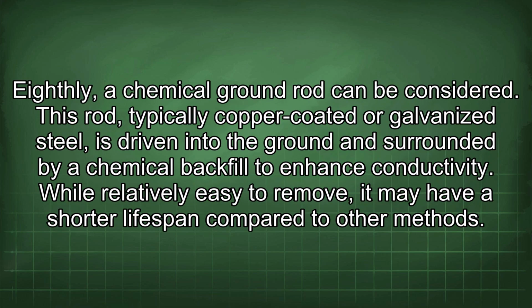Eighthly, a chemical ground rod can be considered. This rod, typically copper-coated or galvanized steel, is driven into the ground and surrounded by a chemical backfill to enhance conductivity. While relatively easy to remove, it may have a shorter lifespan compared to other methods.